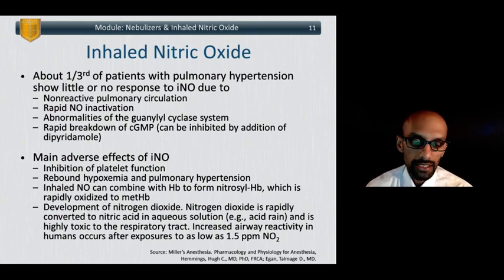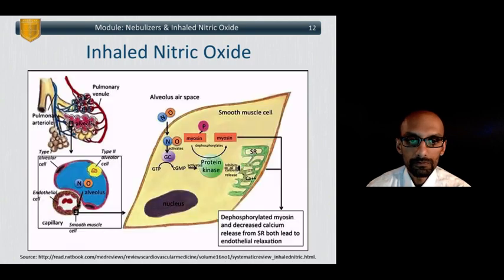There's usually, in the nitric monitor, a measurement for the total amount of exhaled nitrogen dioxide as well. And that tends to be the rate limiting factor in how much you can use it and how long you can use it.